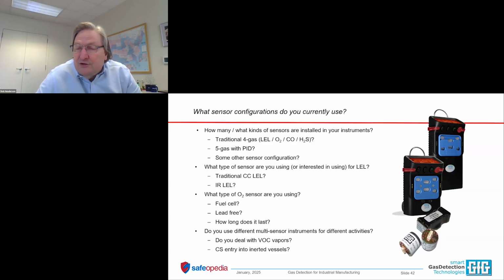A typical oil production site combination nowadays is often a six sensor, or six channel, configuration where we're measuring oxygen, LEL, and PID for VOC gases and vapors, CO, and H2S, because for confined space entry and normal purposes, it's something you run into very frequently. But there is an acknowledgement that if you have the presence of H2S and you're doing hot work, you have an excellent chance of generating SO2, and that takes us up to a sixth channel of measurement. So for these users, that's the combination that makes sense.